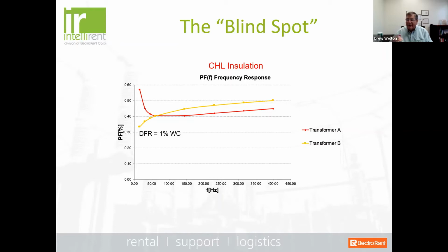I mean, the acceptable range, according to IEEE, is typically somewhere around 4% or higher, or maybe 3.8, and depends on the size and type of the transformer. But 1% water content is certainly in an acceptable range. This particular transformer A had a 3.4% water content, and that is getting up to that critical stage, depending on its operating temperature, as we said before.